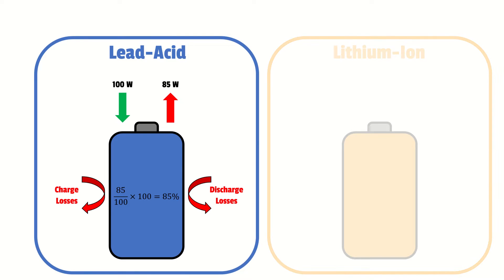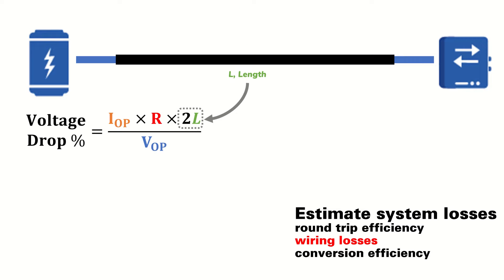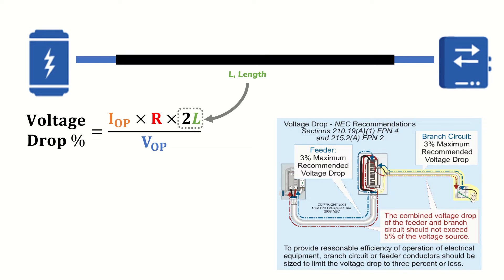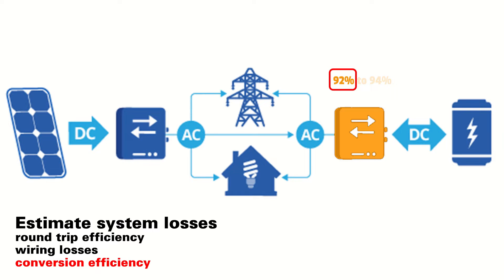For this example we'll use a lead acid battery with a round trip efficiency of 85%, corresponding to a factor of 0.85. For wiring losses, the voltage drop across a wire largely depends on its length, and we typically want less than 2–3% voltage drop, so we'll assume a wire efficiency of 97% or a factor of 0.97. Next, we consider the conversion efficiency of a battery inverter — battery inverters typically have efficiencies ranging between 92 to 94%. In this AC coupled system we'll assume the battery inverter has an efficiency of 92%.